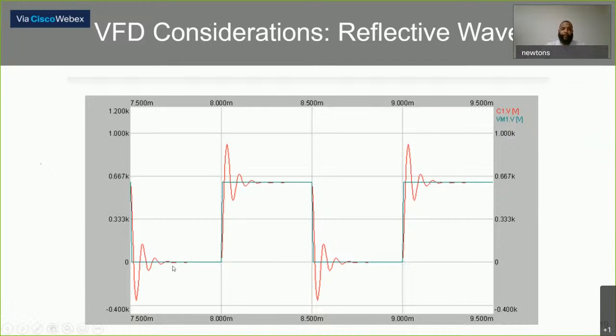So as we discussed before, this is basically a voltage measurement. You can see that when the PWM switches from a low to a high, goes from a high to a low, there's a spike. And this spike, as you see right here, is caused due to the long cable lengths. And that can deteriorate your motors that are non-inverter duty rated or that's not supplemented with motor protection devices to help suppress these out.